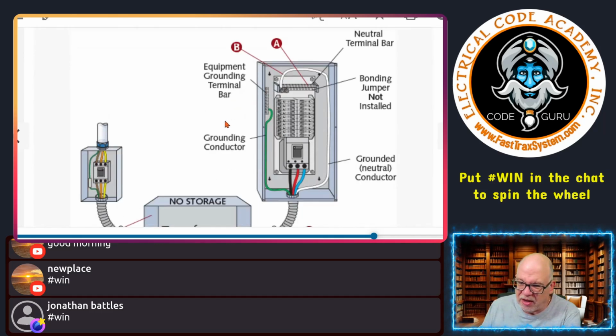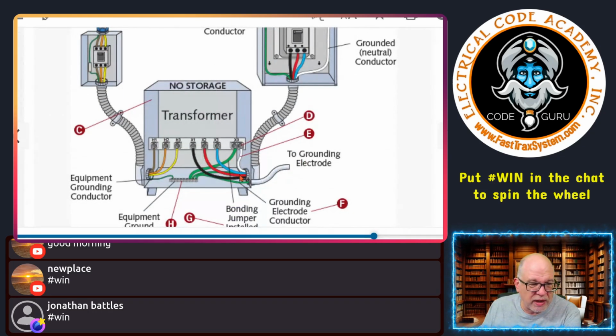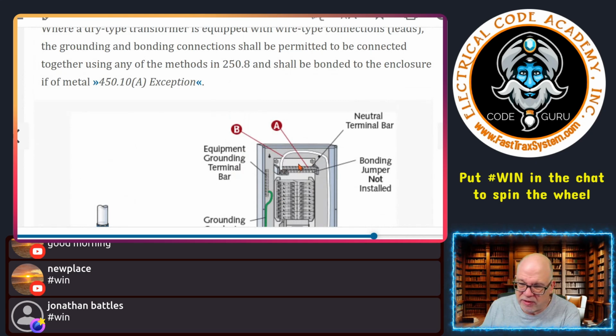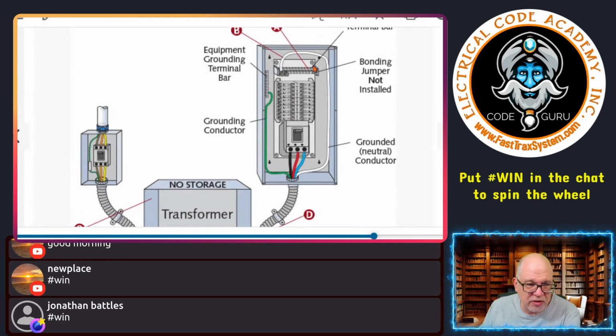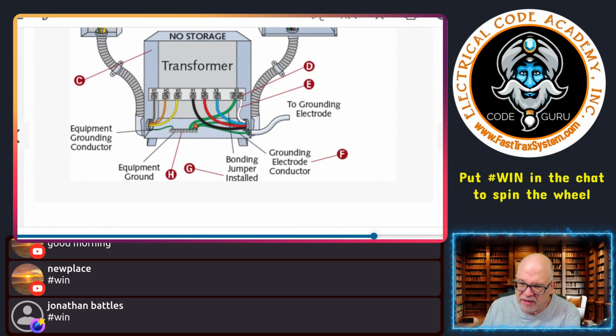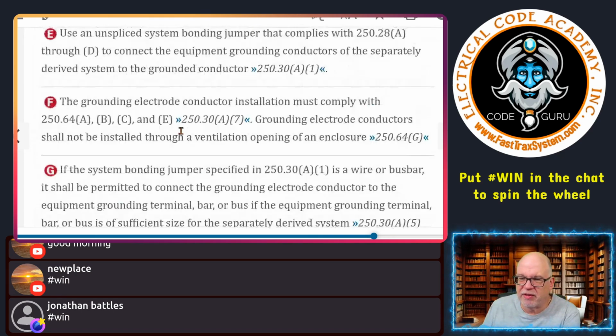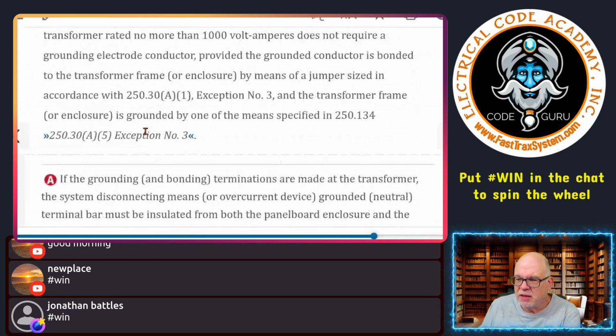You'll also notice something else. The grounding electrode conductor going out to the electrode for this transformer is from here, where the system bonding jumper is installed. Not here, like on the last one. That was only if I chose to put the system bonding jumper here. So it's being done down here, see? Right there. And then here is where it's going out to the grounding electrode, right here. So this is your grounding electrode conductor. It's going out, okay? And this, again, is your bonding jumper right here. That is your system bonding jumper, okay? Kind of paraphrasing all these so we can run through these. All right, so that was A.